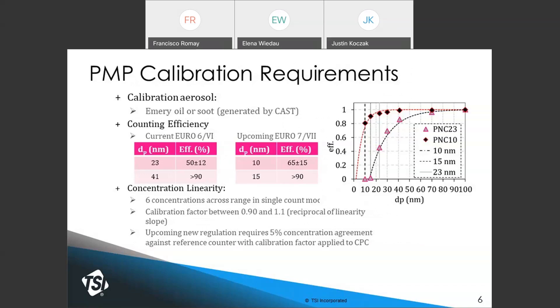For current Euro 6 regulations, still at 23 nanometers, the CPC needs an efficiency of 50 plus or minus 12% at 23 nm and more than 90% at 41 nm and higher. For the upcoming Euro 7 regulations, we're going down to 10 nanometers. The current draft requirement is 65 plus or minus 15% at 10 nanometers, and more than 90% for 15 nanometers and higher.